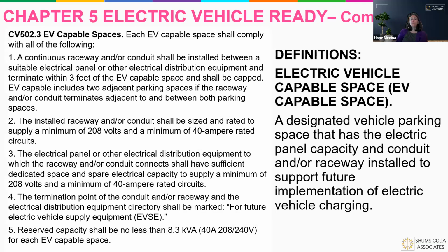Here's the definition for capable space. This one does have the raceway and conduit, which needs to run between the electrical panel or distribution equipment and terminate within 3 feet of where the EV charging space will be, and it also has to be capped. You can use it for 2 adjacent spaces, as we've seen with pictures of one set of equipment serving 2 chargers, one for each space, and that's acceptable per the language.